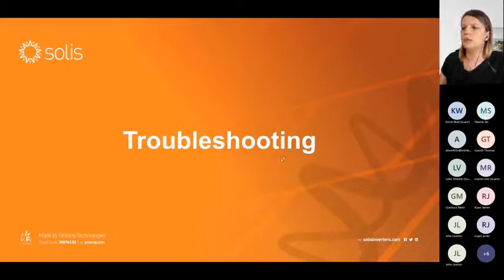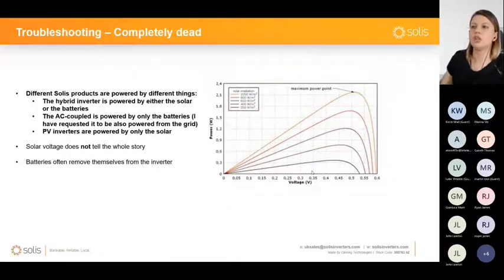Let's talk a little bit about troubleshooting and what type of issues you might have with the inverters. Well, I guess the main problem that you might face sometimes is that you have a completely dead inverter. It's not doing anything. When this happens, you have to keep in mind that the hybrid inverters are powered by solar or by the batteries. If those are not available, the inverter will not start, even if you have AC connection and you have voltage on the AC side.